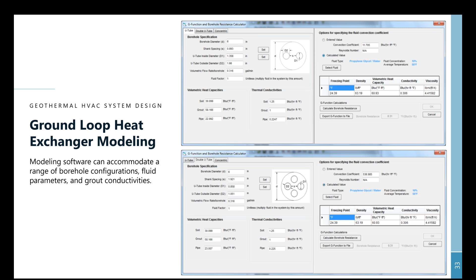So all these parameters that you're entering as you approach the first modeling run, a lot of them you may have to go back and adjust based on how the system is performing. So what does the modeling software give you at the end? It'll give you a simulation. In this case, for this particular software, it can do a simulation for up to 100 years of performance. Typically, we're looking at a minimum of 30 years of performance to establish whether this ground loop heat exchanger is going to perform adequately over time.